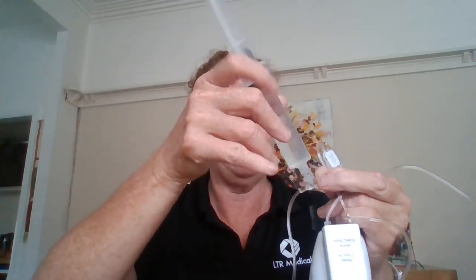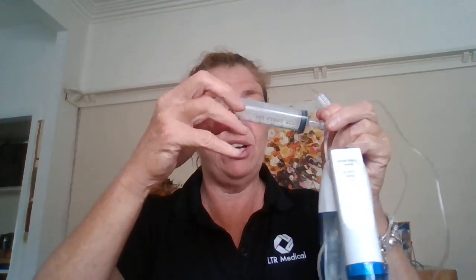So right, we have both of our arrows pointing upwards, and here is our filling port. This is purely just a Luer lock fitting. So as you can see, that is quite easy for me to inject, and at the same time, the balloon within the device is also filling. I'm going to aseptically place the cap back on. You would obviously have those arrows pointing up during the whole filling process. We can also now see that we have our first drop coming out of the end of the line. So that is now primed and ready to connect to our catheter.